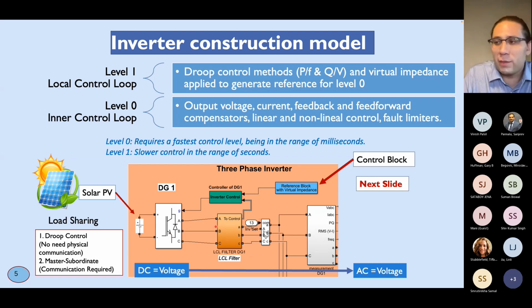So the bottom figure is basically an exemplification of how the DC voltage comes from the sun and is represented as a DC source. And here we use the power electronics to pass through an LCL filter and then connect to the grid. So on this side, we will have a grid going from DC to AC voltage. There are two methods for communication lately. The first is the droop control, the one we utilize, which has no need of physical communication between inverters to share different types of loads. And we have the master-subordinate, which requires a bigger communication system, and it's basically like a traditional EMS or a SCADA system, for the people who are familiar with them, that we can control from different areas.